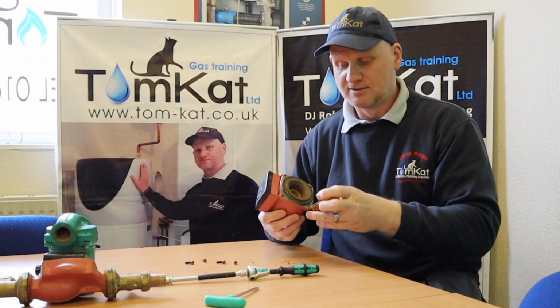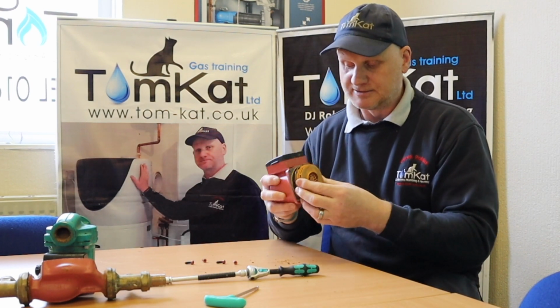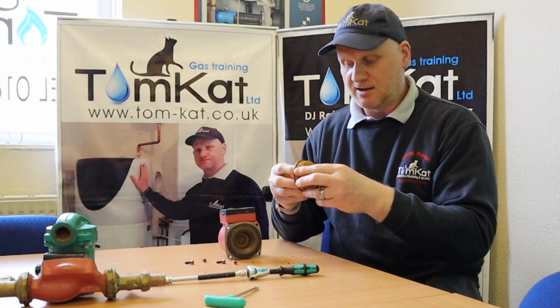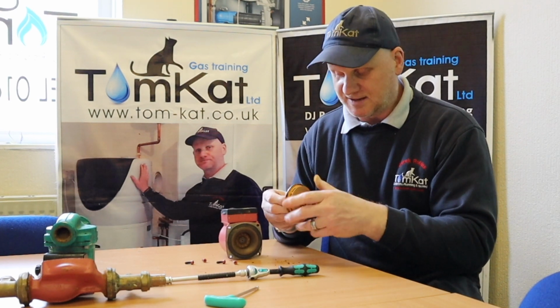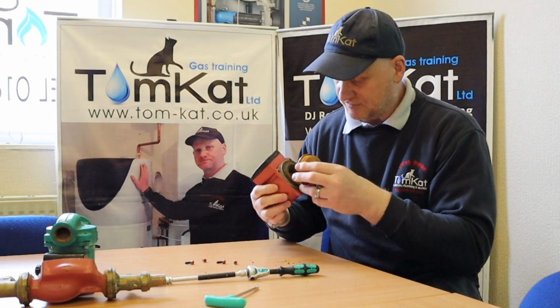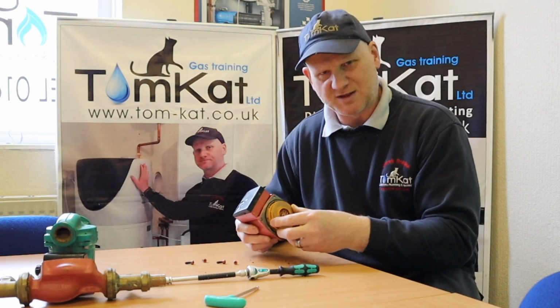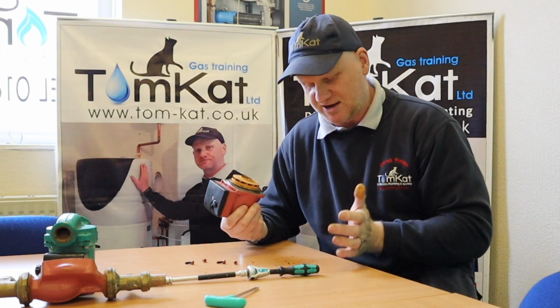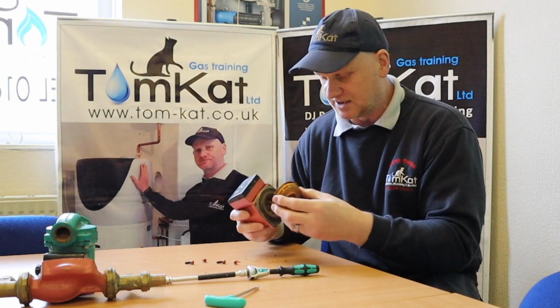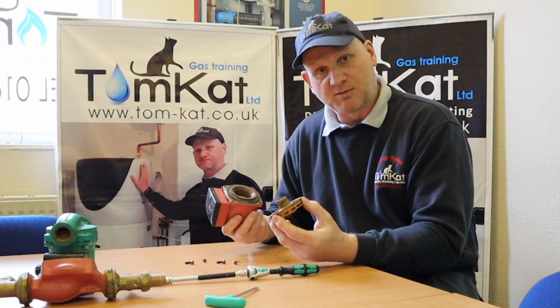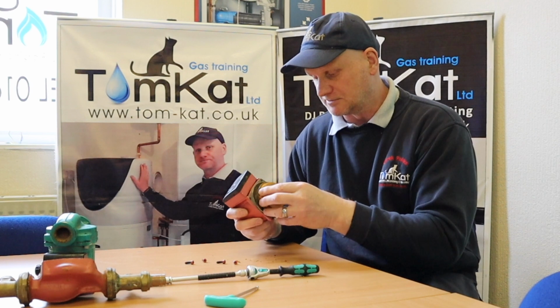Now, the impeller. The impeller is the important part of the pump. It needs to move free, and obviously this didn't move free. It snapped off as I pulled it off, or it could have been snapped off anyway. One of the trainees or ex-trainees has brought this in for me, so this probably wasn't working, that's why it's come out.